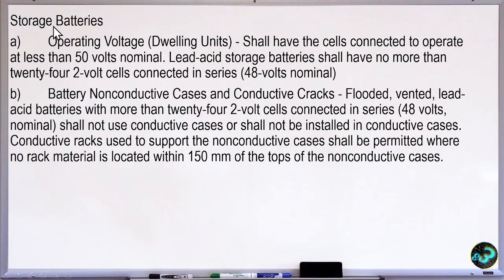So our storage batteries. If we are going to have our solar installed in dwelling units, the operating voltage for dwelling units shall have the cells connected to operate at less than 50 volts nominal. So it cannot exceed 50 volts, our voltage for dwelling units, that is for the batteries.